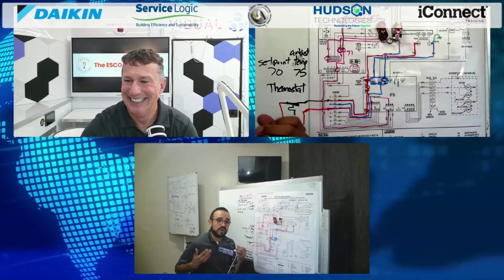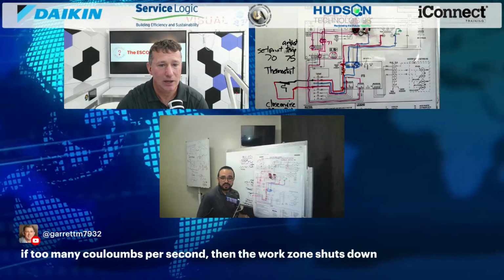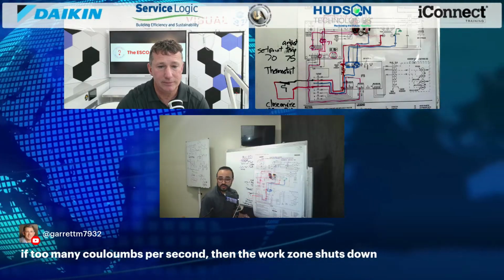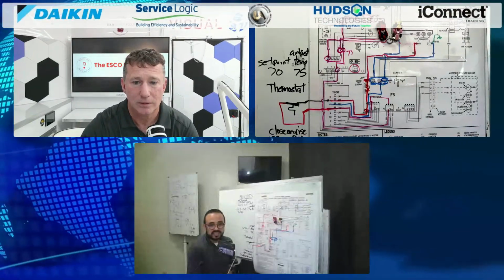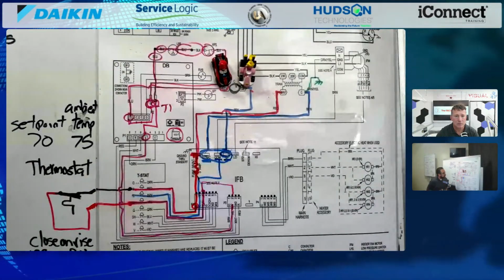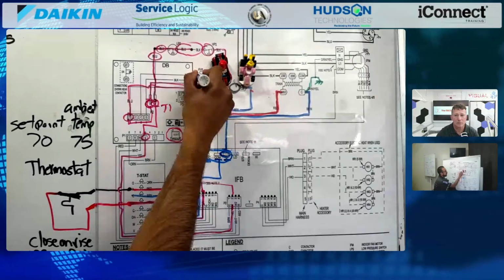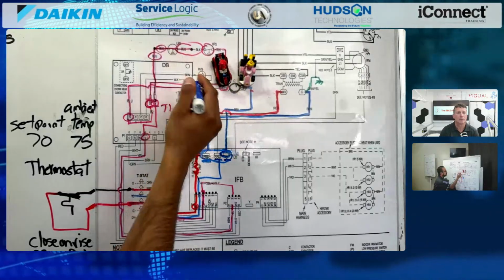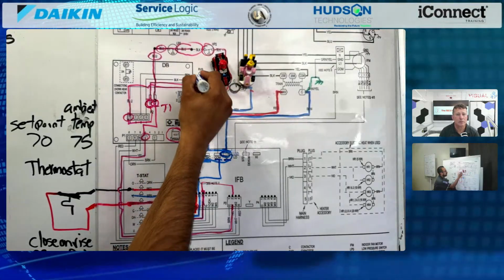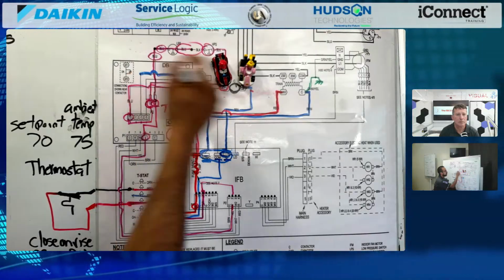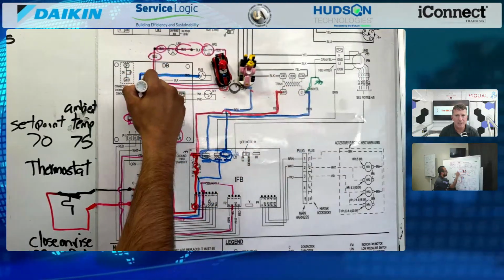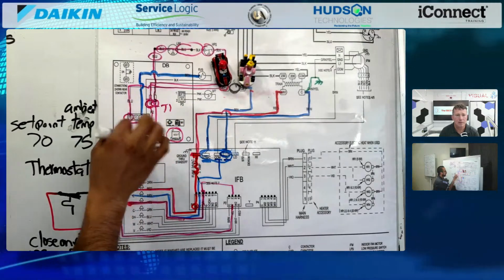That's right, because this is a heat pump. So if I want to call for cooling, I also need to send power to my reversing valve. So I've got to first identify my reversing valve, which is right here, RVS. We're going to use brown, in this specific case they're using it for common, so brown I'm going to treat as common. It goes to common right here, and it's actually 4, 3, 2, 1.